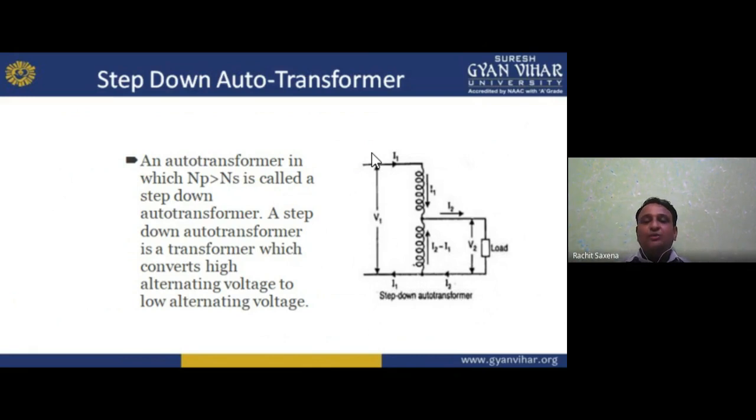So if I am talking about the power system, my dear student, only at the generating station do we have the step up transformer. Elsewhere we use the step down transformer. We convert 11 kilovolt into 800, 765 or 400 kilovolt. Then 765 or 800 to 400, then 400 to 220, then 220 to 132, 132 to 33, 33 to 11, then 11 to 415 and 220. So secondary distribution, primary distribution, primary transmission, and secondary transmission.